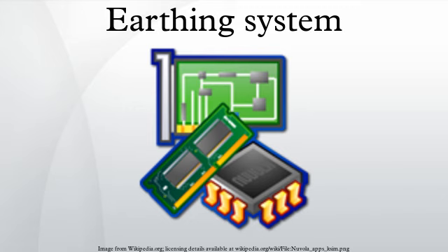Safety. In TN, an insulation fault is very likely to lead to a high short-circuit current that will trigger an overcurrent circuit breaker or fuse and disconnect the L conductors. With TT systems, the earth fault loop impedance can be too high to do this, or too high to do it within the required time, so an RCD is usually employed. Earlier TT installations may lack this important safety feature, allowing the CPC and perhaps associated metallic parts within reach of persons to become energized for extended periods under fault conditions, which is a real danger. In TN-S and TT systems, a residual current device can be used for additional protection.